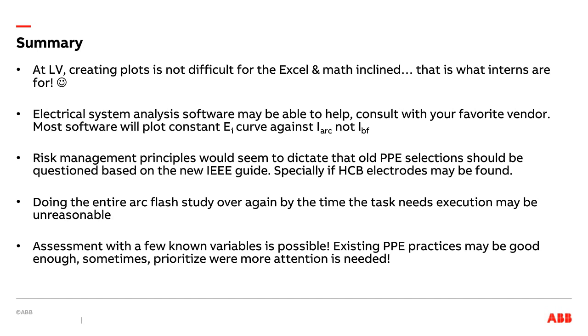You could work with your electrical system people to create the charts, but on the other hand, if you already have a model and you're going through this trouble, it may just be easier to do an updated arc flash study, which obviously is the best thing to do. It's important to understand, again, that this is all about controlling risk, and whether the PPE you have hanging around, the PPE you're used to using for that task, based on the new calculation method, is good enough. It may not be perfect. It may still be too much. You may want more margin, and you can easily tweak the numbers in the previous chart.